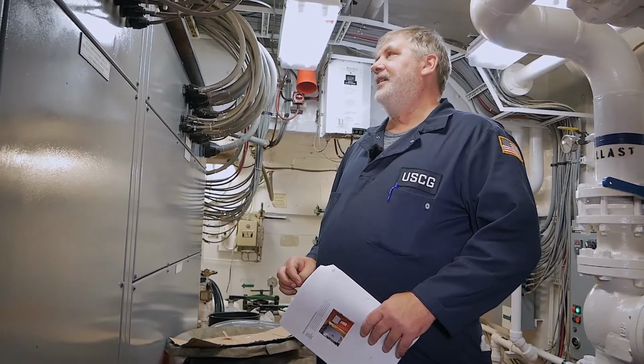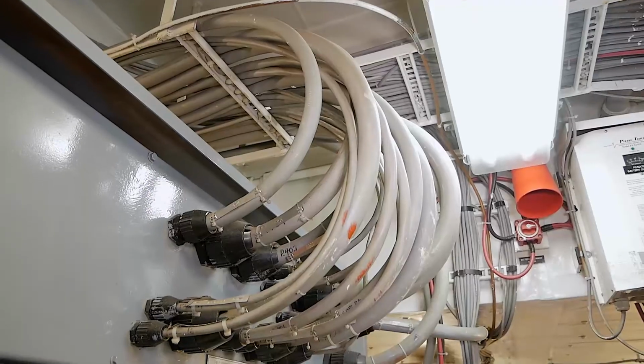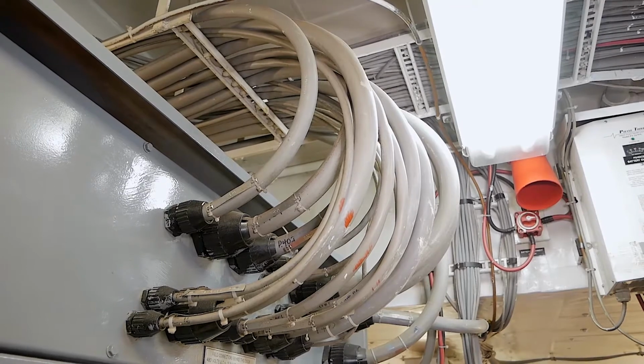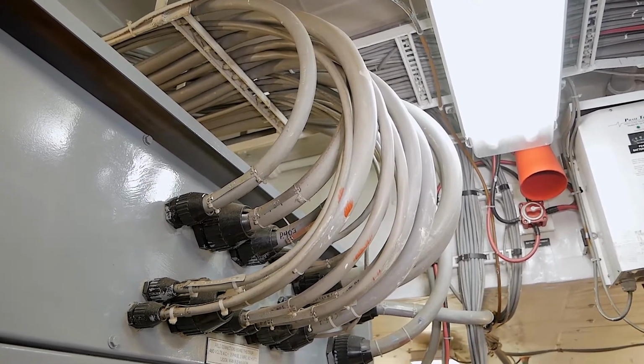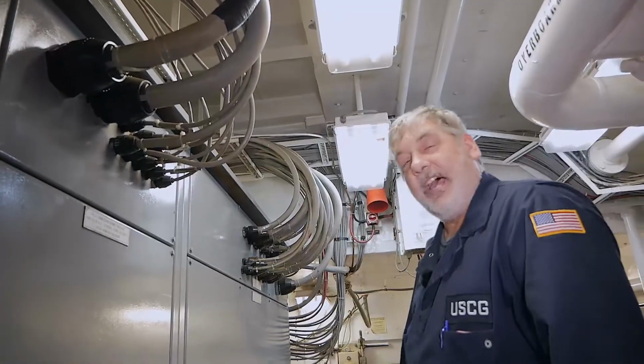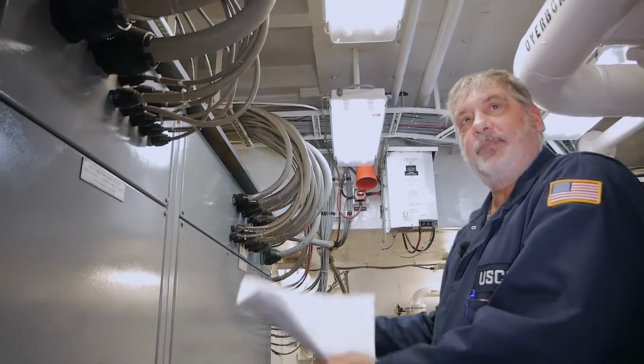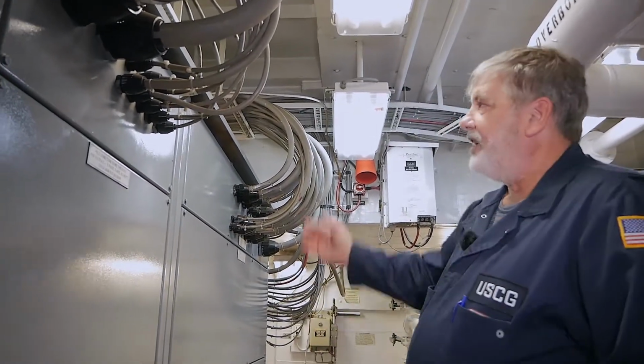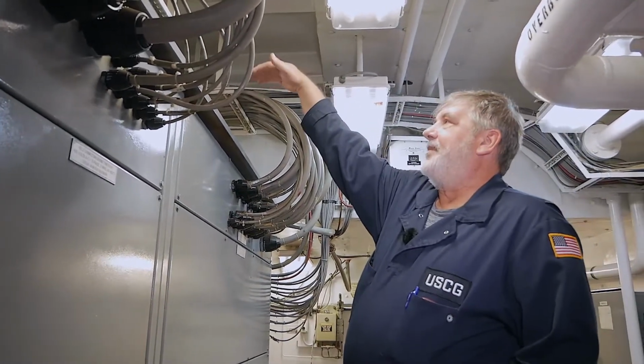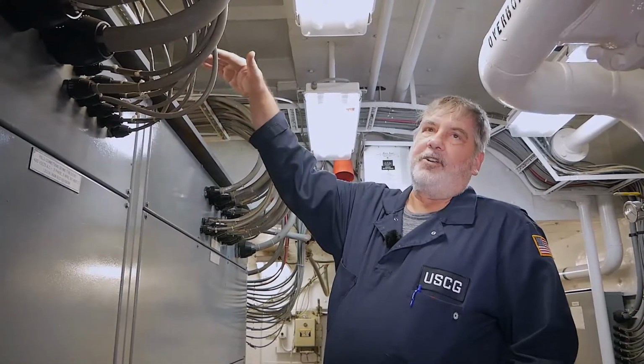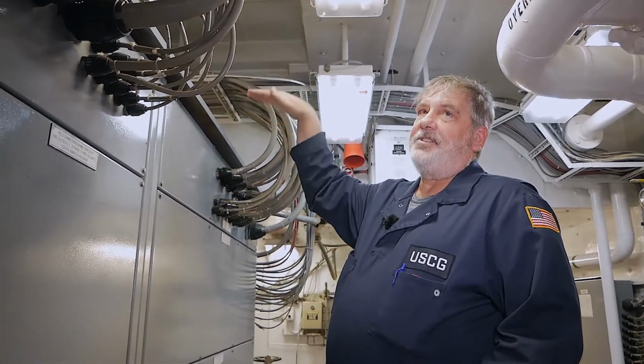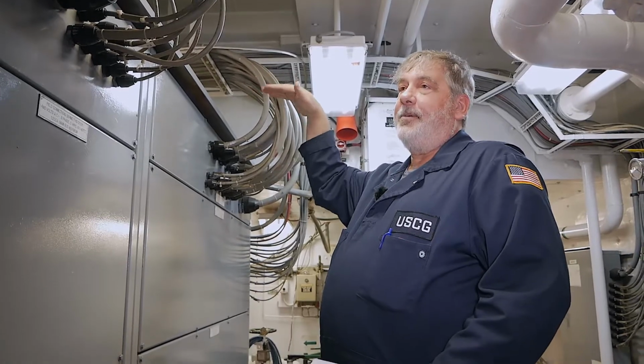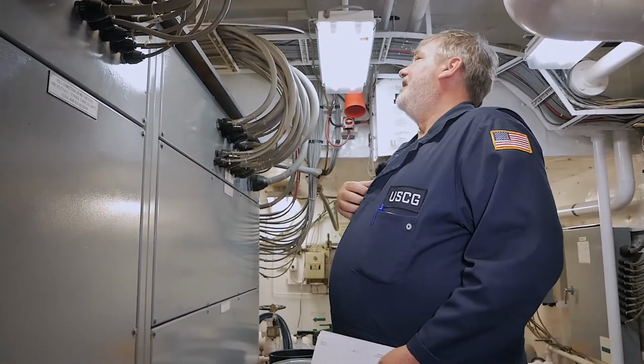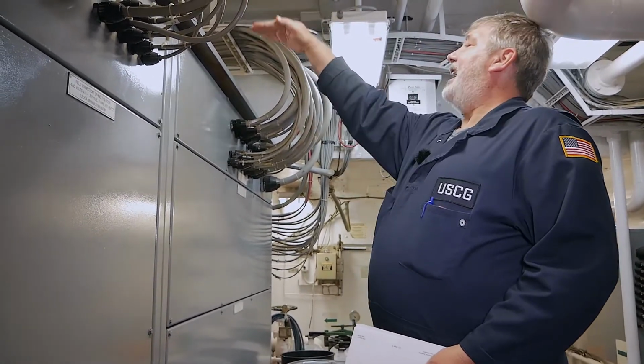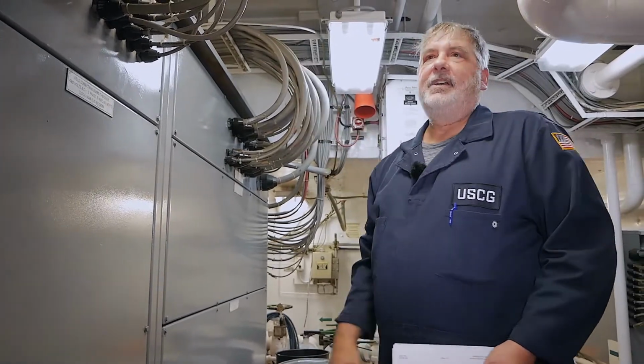switchboard. As you can see, all the cable entries to the switchboard come down and go in from the back. A lot of times with switchboards, the cables will come in from the bottom. The top of the switchboard is a vulnerable place, especially if you penetrate it with cables there. So the top is drip proof and intact.